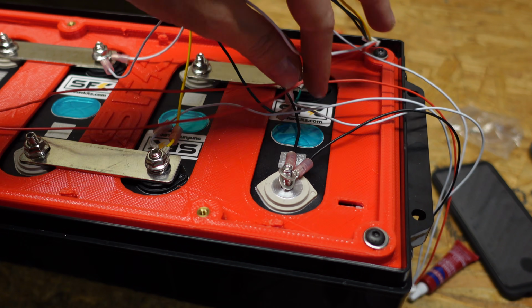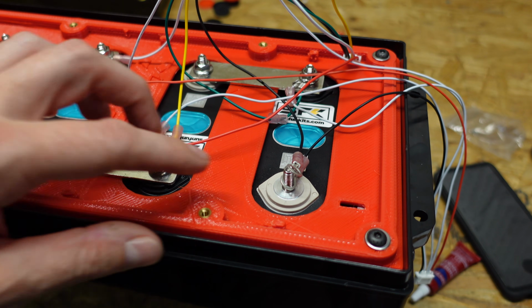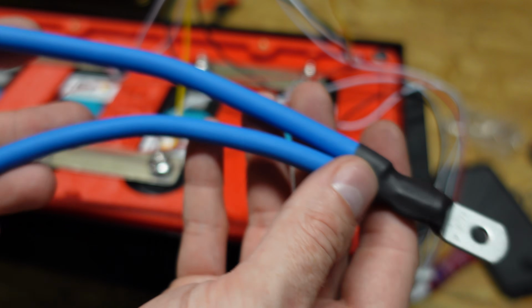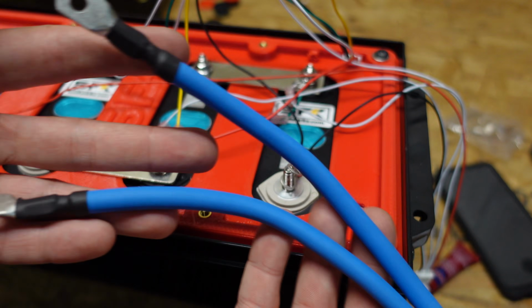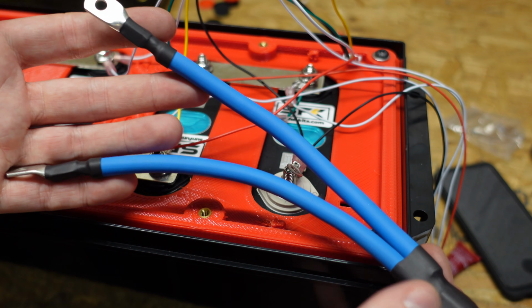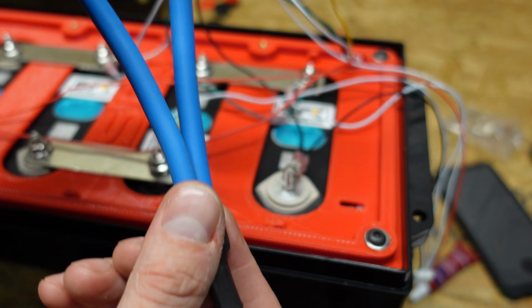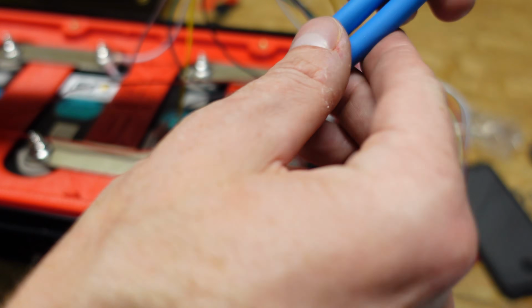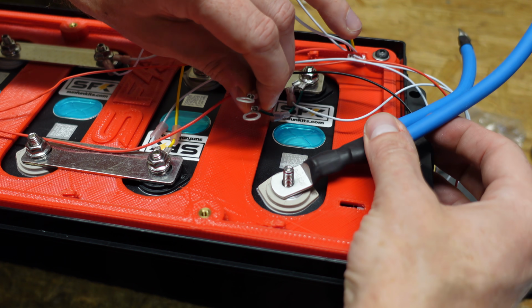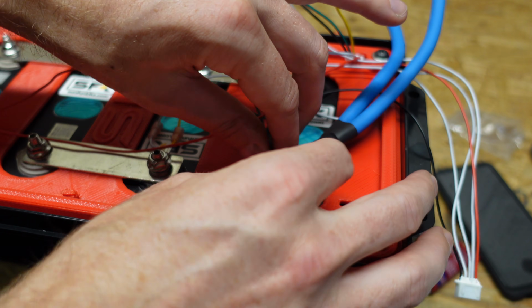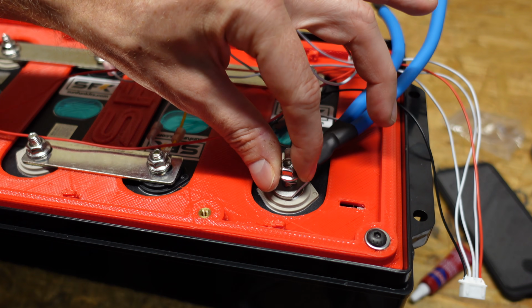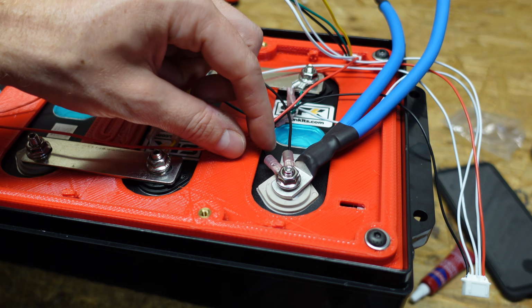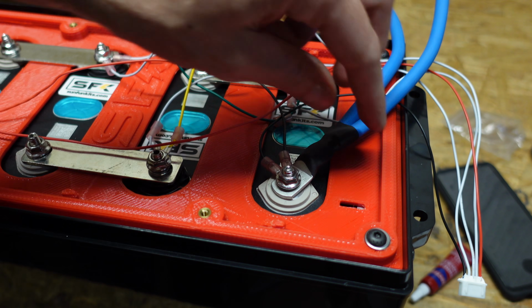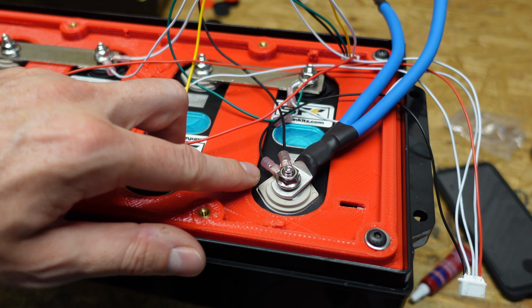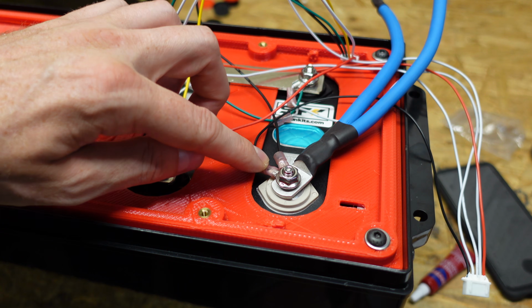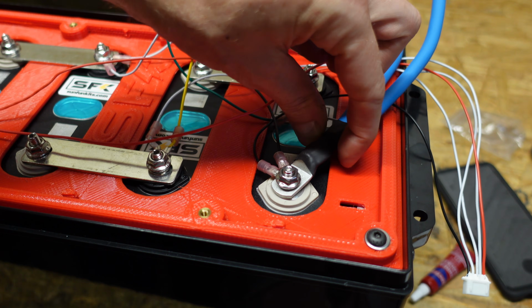Now I'm up to the main negative connection. Before I put the nut on, I need to install the cable that goes from the battery to the BMS, which is a blue cable in a Y shape with 3 lugs. The single lug goes on the battery post first, then both ring terminals, then the flange nut. Order is very important here — you want this lug against the battery itself, with nothing like a washer or ring terminal between the battery pole and the lug.